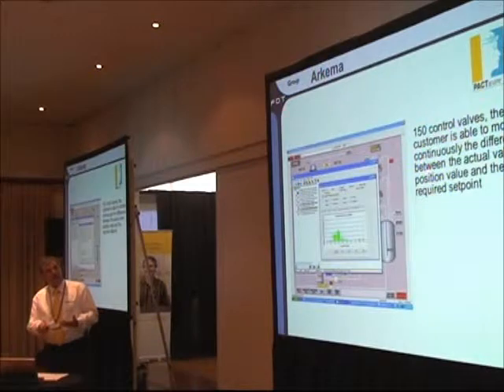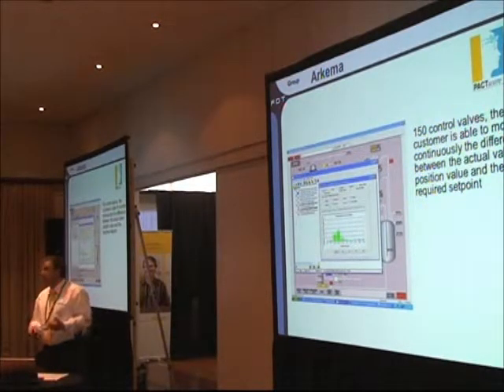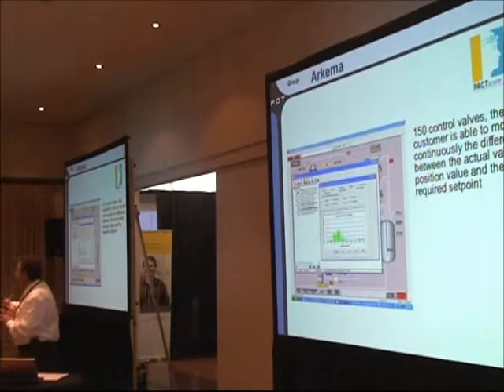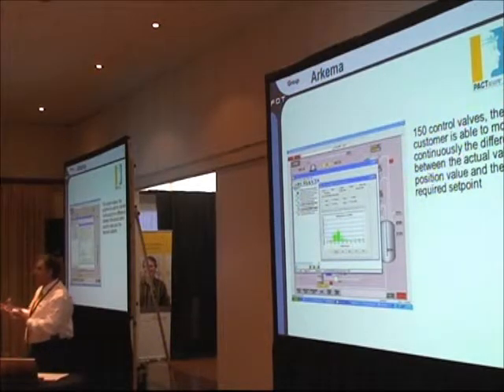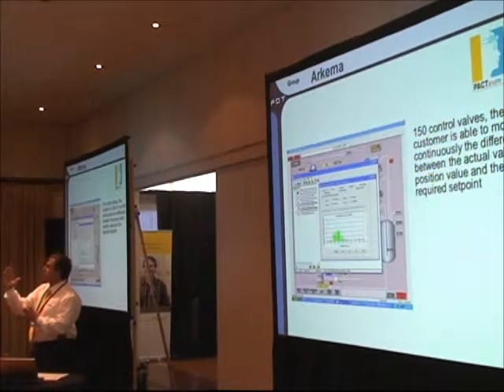Important here, for example, is to see the difference between the actual valve position and the required set point, and whether they are working in a good area or a false area. This way they could determine in advance if the valve was running away from the optimal setting point.